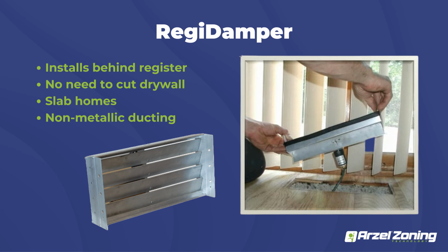You can get some potential bleed by on this specific damper, but it allows you guys to zone things that somewhat, you know, there's no other options for. So it's got its uses out there. Just keep in mind it does have those galvanized blades, so you do get a little bit of bleed by on it. And if your static pressure gets too high in that system, you could also get a whistle as the air blows by those blades. So just keep in mind, you know, when you guys are designing that job, how small a ductwork you guys are going to do, or how small a zones you're going to have on the panel.